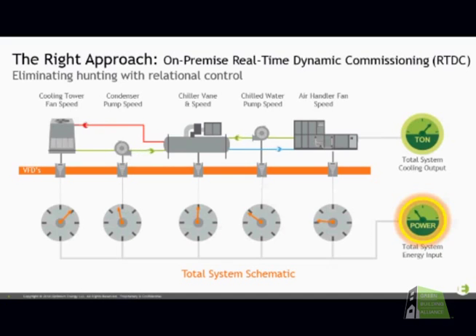And this is why condenser water pumps sometimes you might still see as constant speed, because the thought is that you want to always run those at 100% in order to maximize your chiller efficiency. And it will increase the chiller efficiency, but you might be using additional power that you don't have to on the condenser water pumps. And just one other note, when you talk about variable speed drives, what that really means, we know from the affinity laws for an electric motor, so this is true for any electric motor, not just on the pumps, but on the cooling tower fan, and also the compressor for the chiller itself.